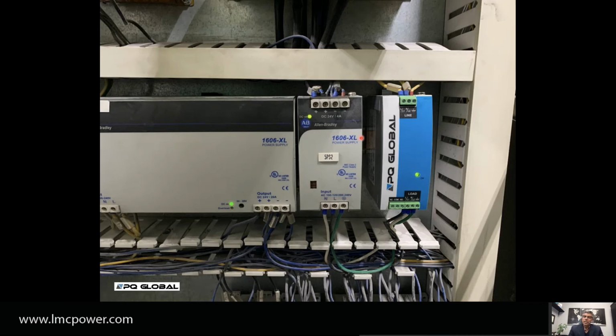No, but what we did is they were having problems with their controls. A lot of times at the very end of your electrical system, your equipment is very sensitive, not just to transients, but also to electrical noise. Electrical noise is the same issue as transients, only it's smaller amplitude, but it still causes havoc in terms of the controls. So what we did is, every one of their power supplies, their Allen Bradley power supplies, they wanted to protect not only against transients, but also against electrical noise.